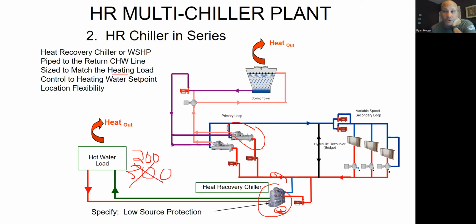If you happen to have a weird scenario where, hey, I've got this building and they always need exactly 300 tons of cooling and exactly 300 tons of heating, can I just put a heat reclaim chiller in, put no other chillers in, and just have that one guy shove heat between these two places? Yeah, you could do that. But the problem is, what happens when it doesn't actually end up being exactly the same loads? There's nobody left to make up the difference. So in that scenario, you'd have to size it for the higher of the two loads. So say it was 300 for cooling and 250 for heating. You'd size it for 300, knowing that you had more cooling capacity than heating capacity, so you'd still need a cooling tower to take care of the other 50 tons.